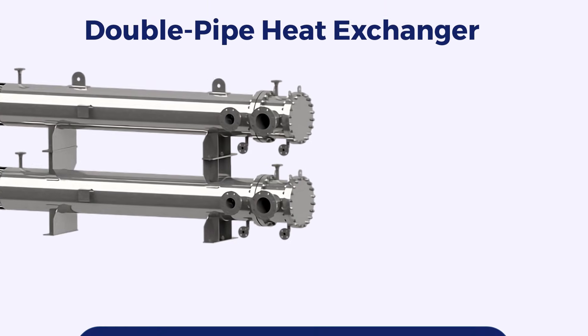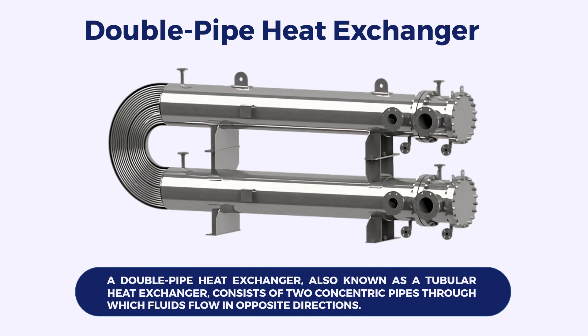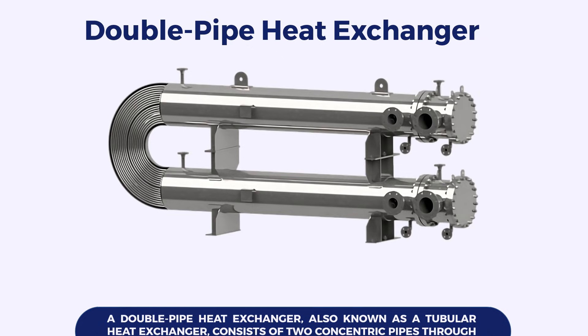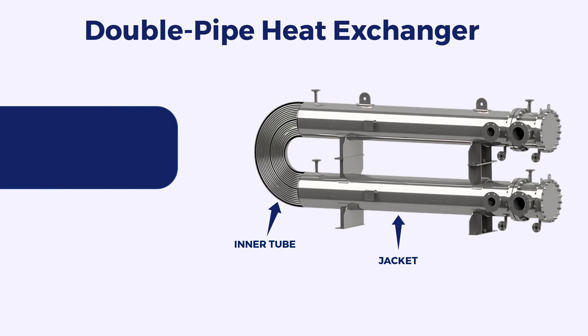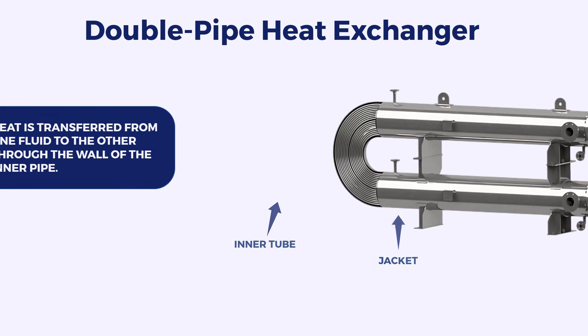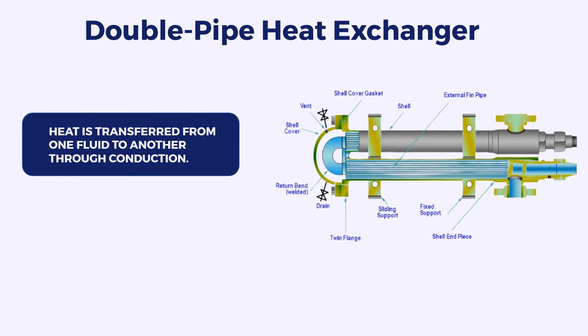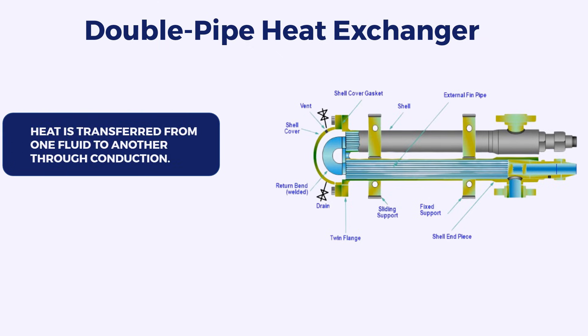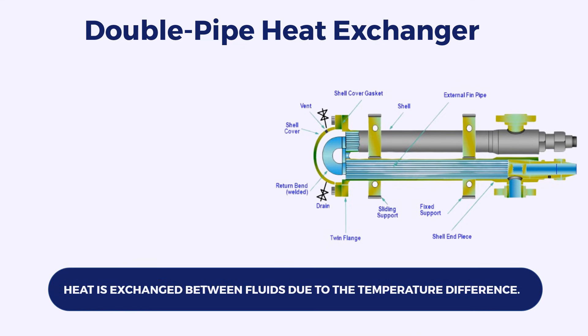Double Pipe Heat Exchanger. A double pipe heat exchanger, also known as a tubular heat exchanger, consists of two concentric pipes through which fluids flow in opposite directions. The inner pipe is known as the inner tube, while the outer pipe is called the jacket. Heat is transferred from one fluid to the other through the wall of the inner pipe via conduction. As the fluids flow through their respective paths, heat is exchanged between them due to the temperature difference.